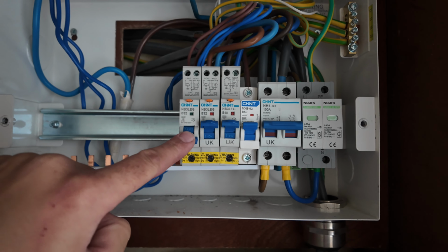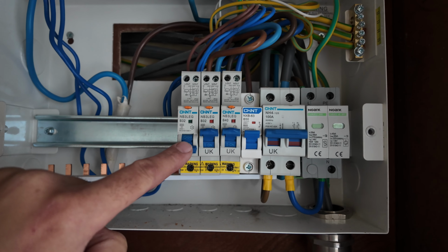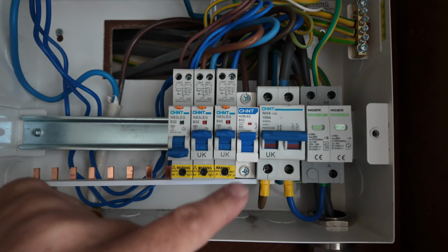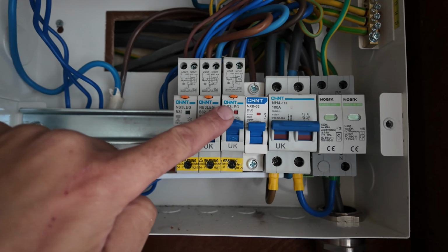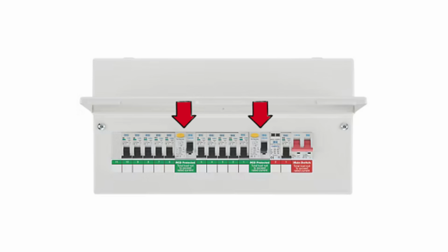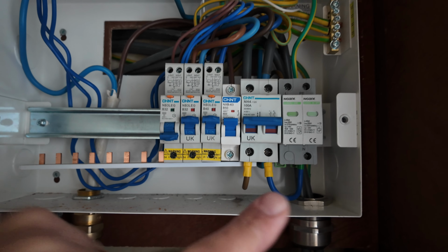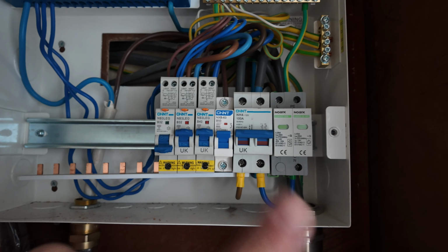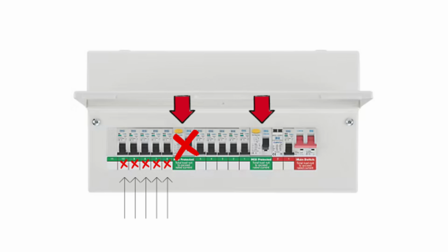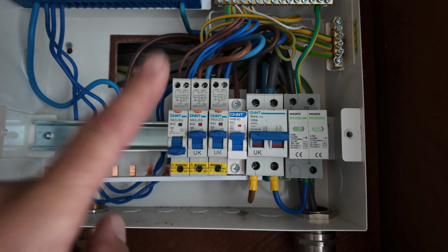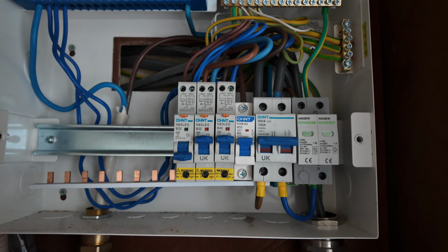Now, the reason I say that is because many consumer units have an RCD unit. So an RCD unit is basically what these units have built into them individually. Now, there are lots of consumer units out there that have an RCD unit which controls many circuits at a time. And that can be problematic because if you have an RCD that trips, that one RCD trips, but it takes out multiple circuits. So you'll see that the RCD would have tripped and then all of these will be on, the circuit breakers will be on, and you won't have a clue which circuit it is.